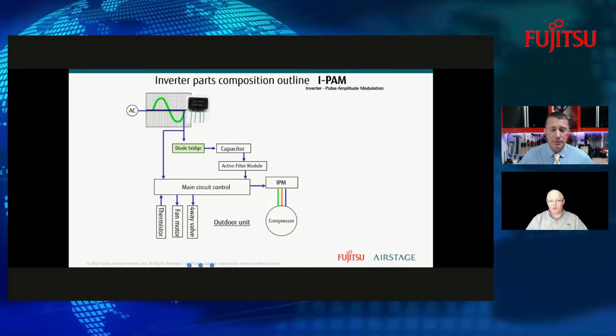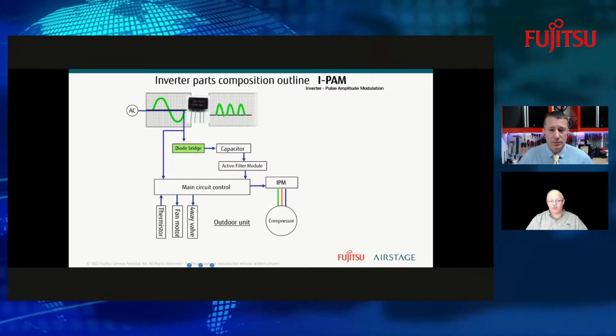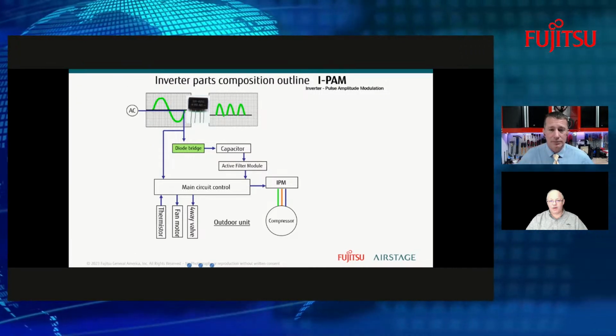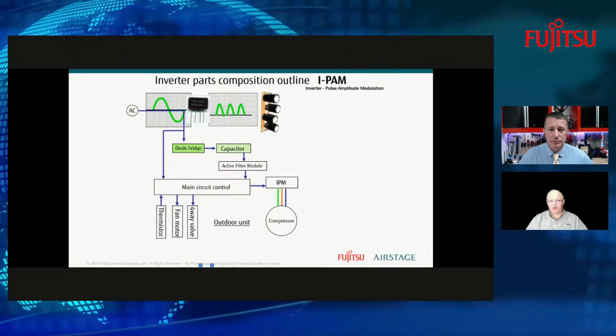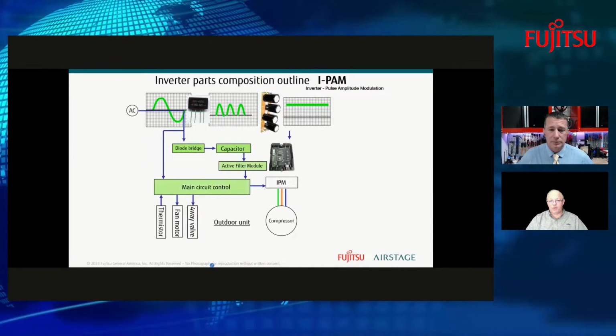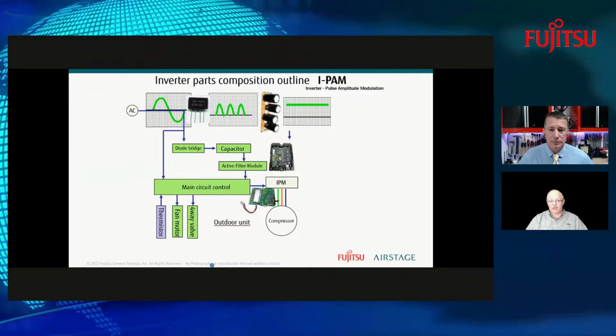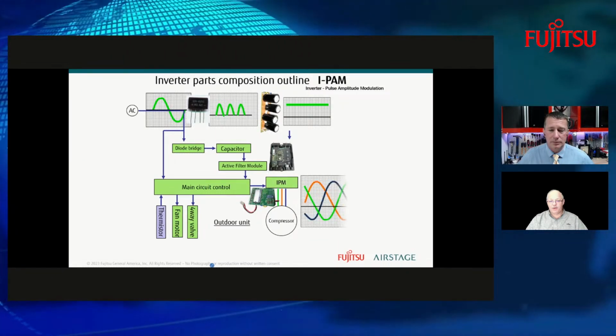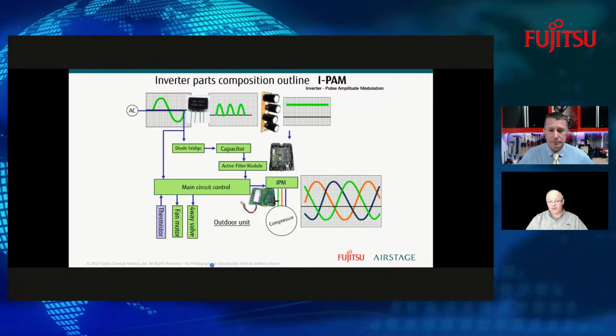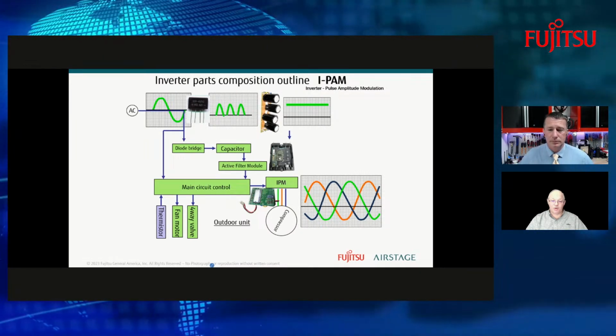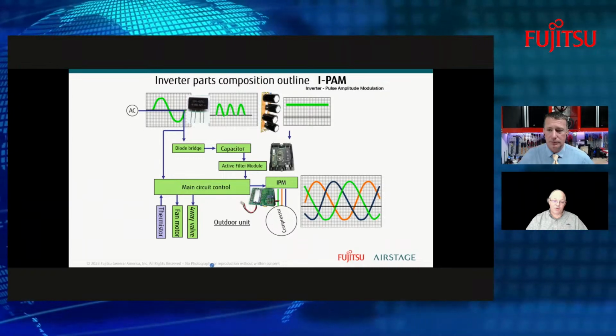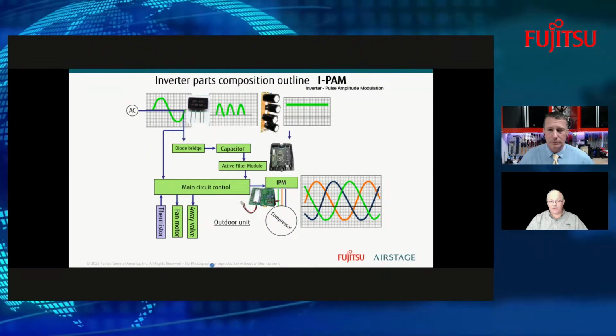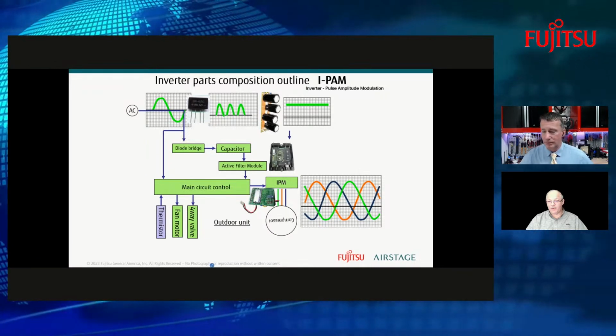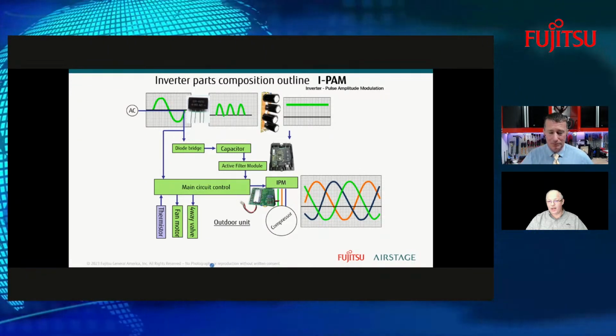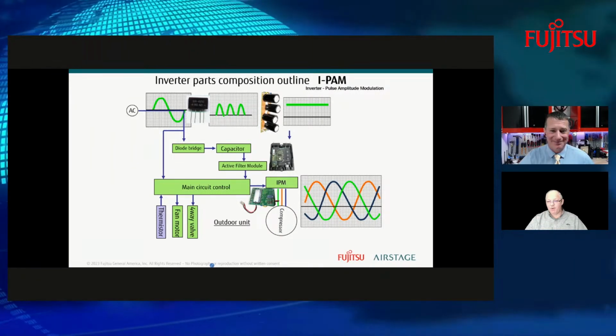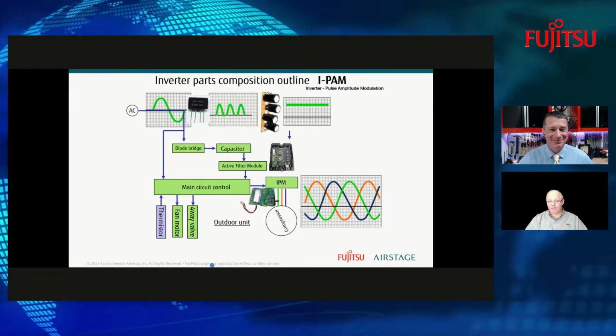So as you're looking at components, we're going through the diode bridge, which you see there in that little green. Right. We go through the rectification of that. We go through the capacitors. From the capacitor, we go through the active filter module. We're going through a main circuit board. The main circuit board is going to feed the IPM, which is what controls the speed of the compressor. And then the main circuit control board is also getting information from thermistors, and it's also sending information out to the fan motor and the four-way valve. So that's just kind of a quick look at how that's happening, component-wise. Yeah, who's doing what? Yeah.